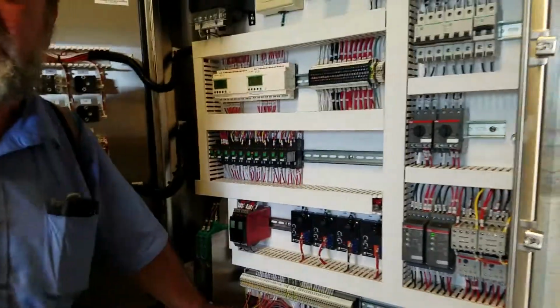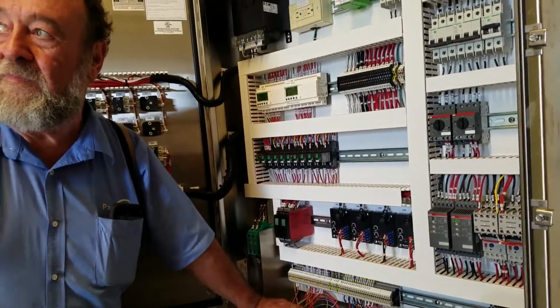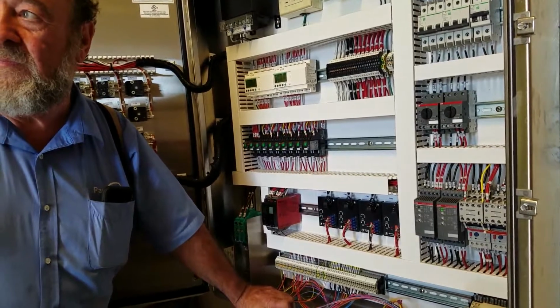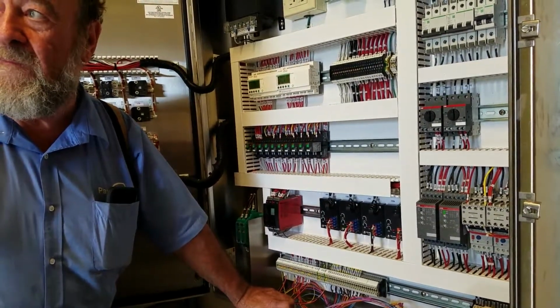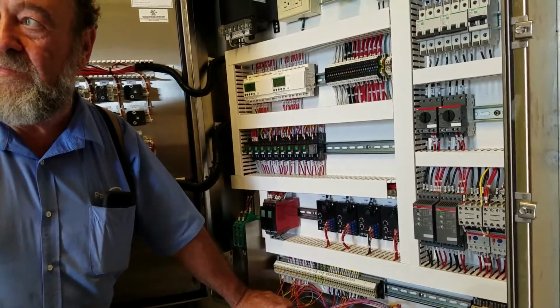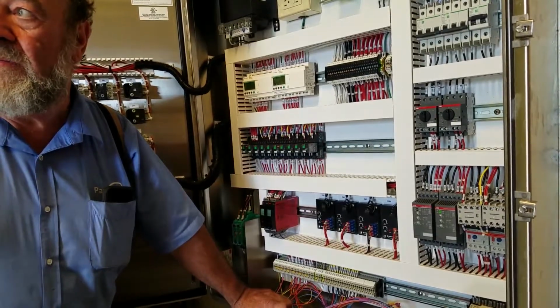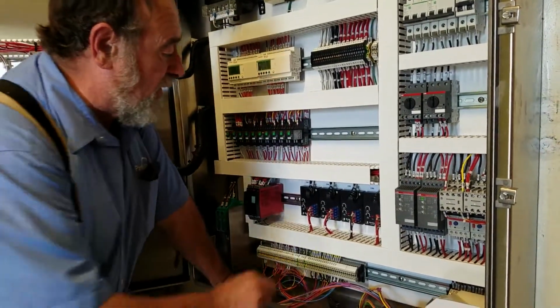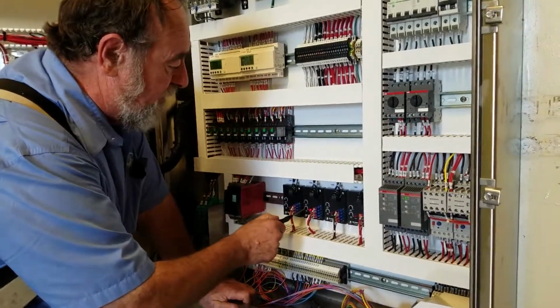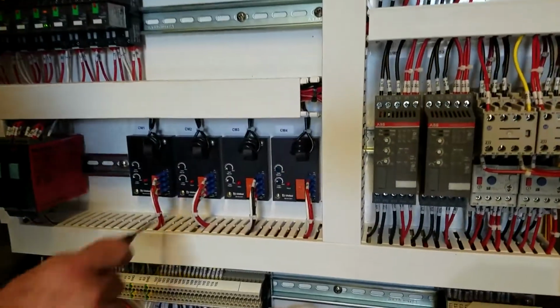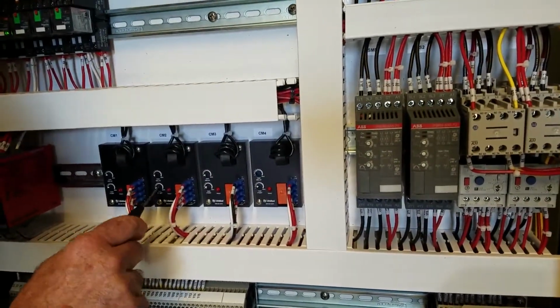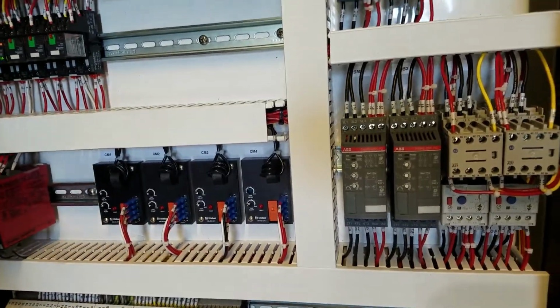When you trip out on that bottom overload, or that one that you set the sensitivity on, do you need to do that loaded? Just do it with it running. Okay. I will put it down to the point where it trips and shuts down. Boom, it just shut itself off. So now you just reset the panel door again? Yep. Just hit the button on the door.